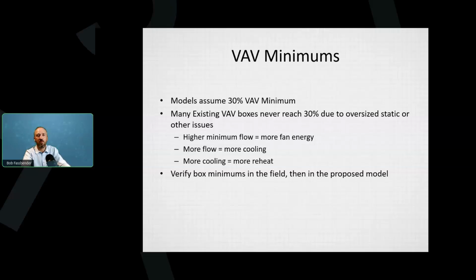So usually a place to save energy in an existing building is checking the VAV box minimums. And when you're redesigning a building, you want to make sure that the box can operate as low as it safely can, because you're going to save energy in three different ways by keeping it at its lowest feasible airflow.